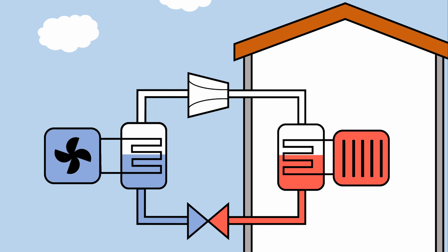Even when it's freezing cold outside, there's still some energy in the air that can be used to evaporate the refrigerant. To extract as much heat from the outside air as possible, air-to-water heat pumps use a large fan to blow air over a refrigerant-filled heat exchanger. This part of the system is called the evaporator. The refrigerant in the evaporator is then compressed using an electrically powered compressor.